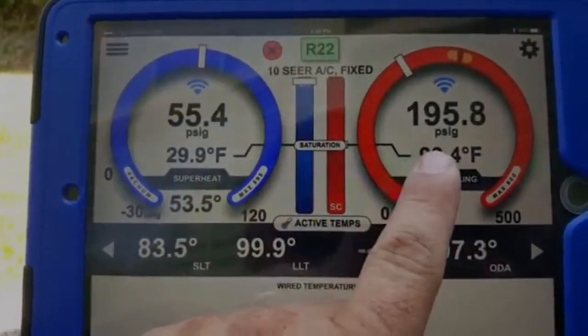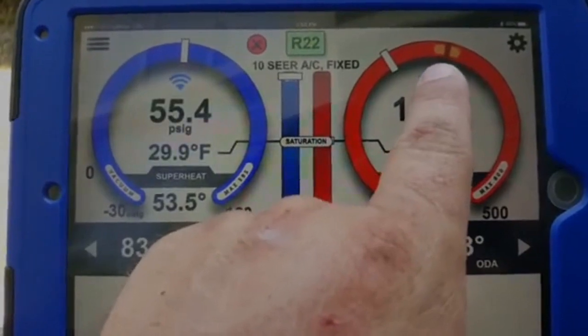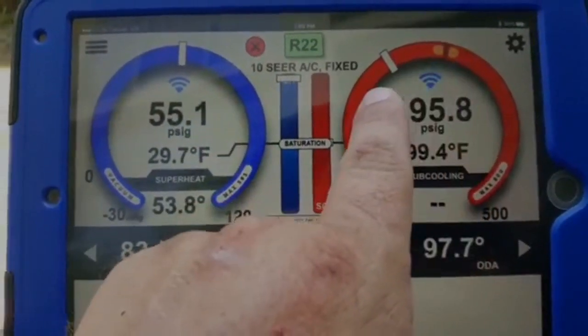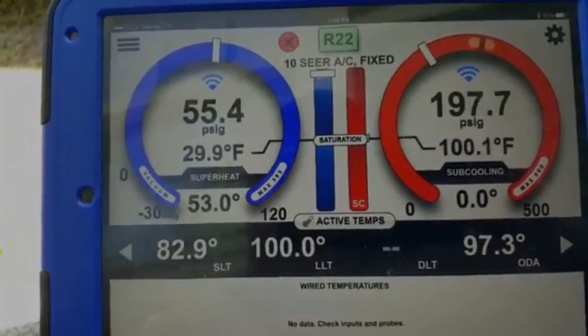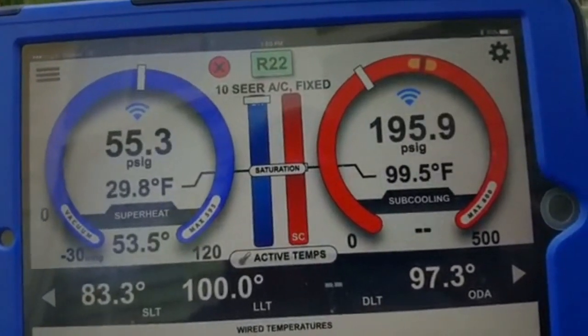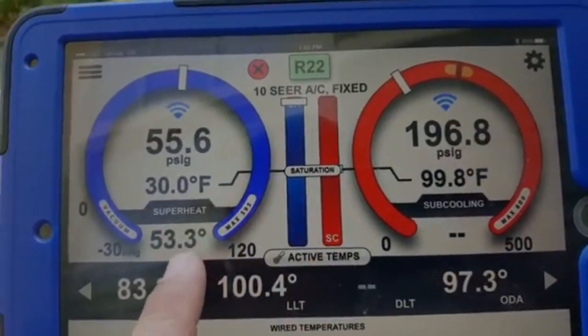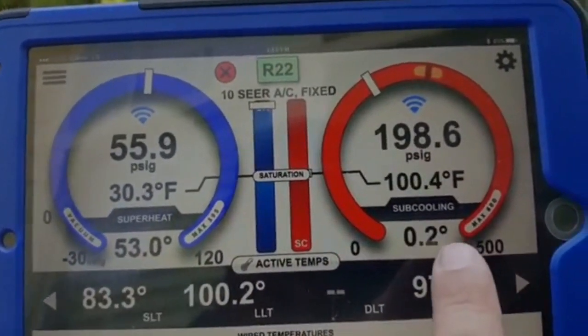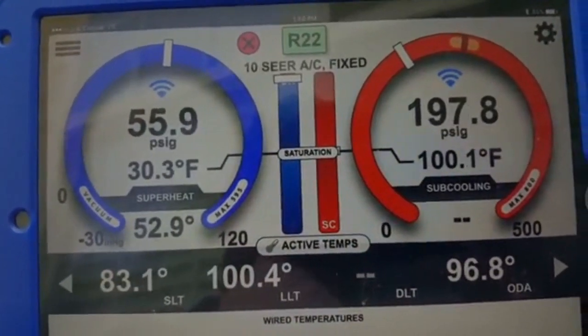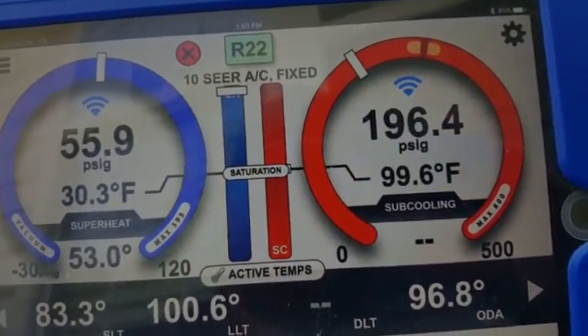Guys, looking at our pressures here, 195. Our target for 10 SEER, this is 12, but it's not going to be too far off. Big difference anyway. 55 when we have 85-degree return air is going to be way too low. Superheat's way too high. No subcooling, definitely low on charge. So we'll see what they want to do.